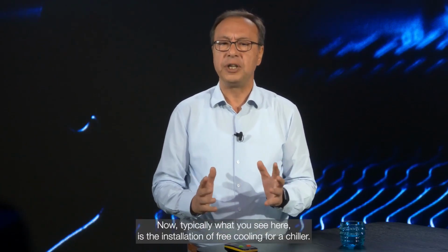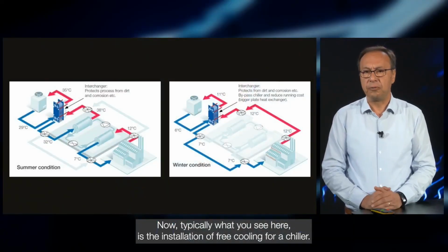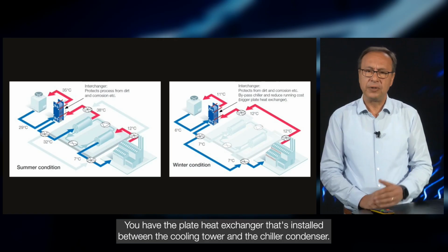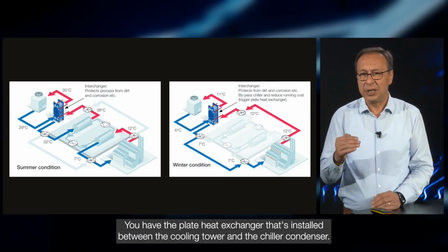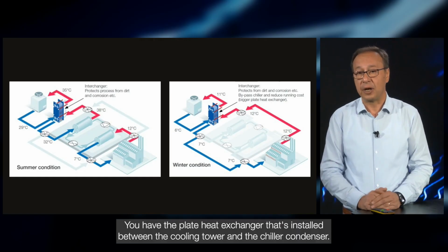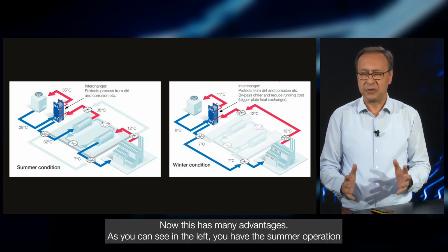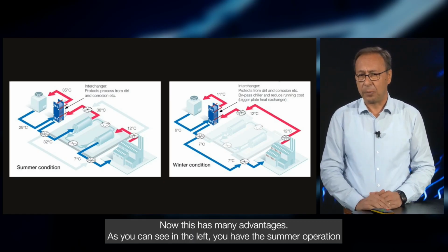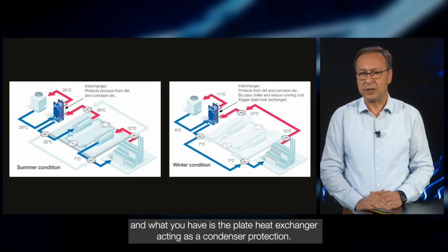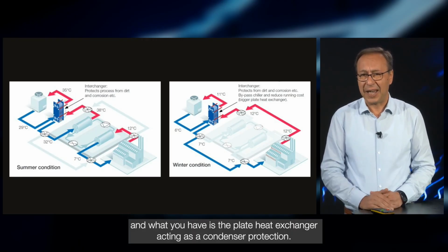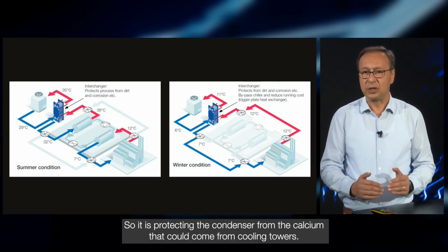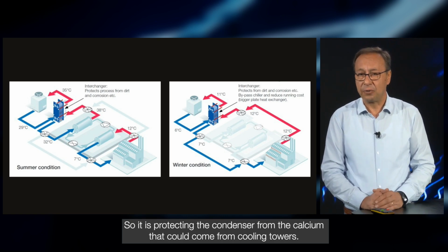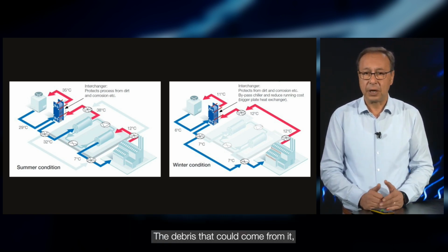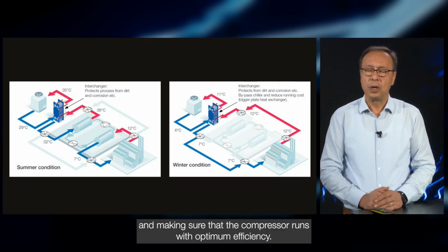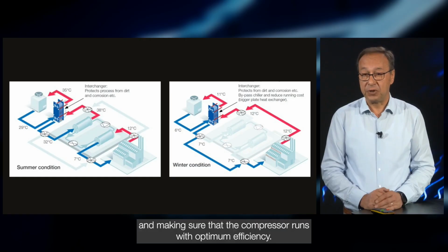Now typically what you see here is the installation of free cooling for a chiller. You have the plate heat exchanger installed between the cooling tower and the chiller condenser. This has many advantages. On the left, in summer operation, the plate heat exchanger acts as condenser protection. It protects the condenser from the calcium that could come from cooling towers and the debris, and makes sure that the compressor runs with optimum efficiency.